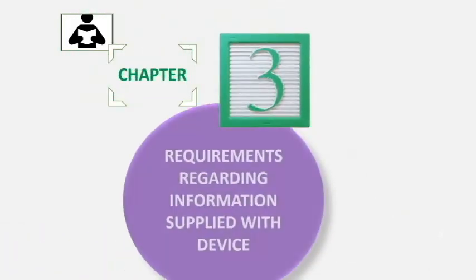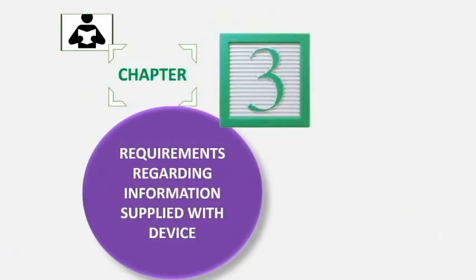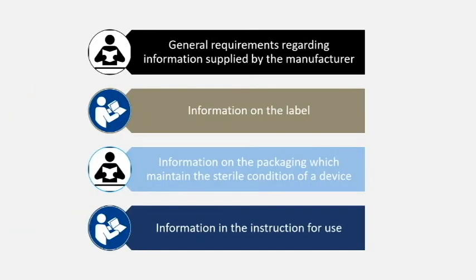Chapter 3 deals with requirements regarding the information supplied with the device, which covers labeling. In general, labeling consists of both the label and instructions for use, including operator's guide, manual, or service manual. It has four subclasses: the first covers labeling of the device, the second covers information specifically given on labels, the third covers information given on sterile packaging, and the fourth covers information in the instructions for use.